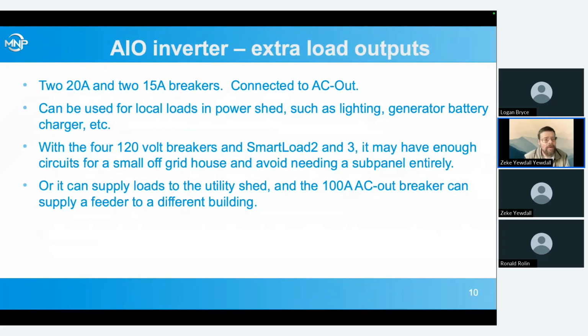We also have all these extra circuit breakers in there, those 4 more circuit breakers to the left of the smart load. And a lot of people have said, what do I do with these? Well, there's a lot of possibilities. Often, if we're doing a separate power shed, we have power needs in there, such as our lighting, our generator, battery charger. And if we're sending a 100 amp feed over to the other building that's the main house, we may not want to put in a sub panel in the power shed and deal with pulling off that 100 amp feed. Might be easier to just power some of those circuits directly off those auxiliary breakers.